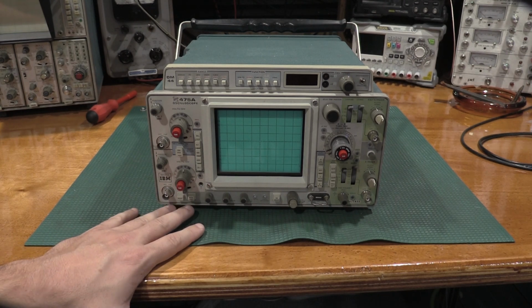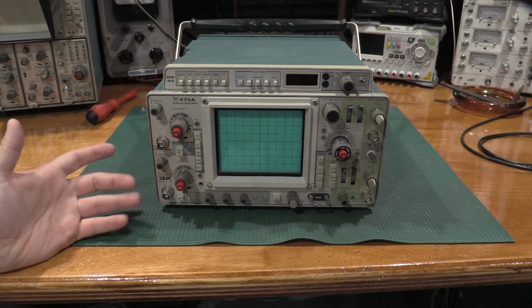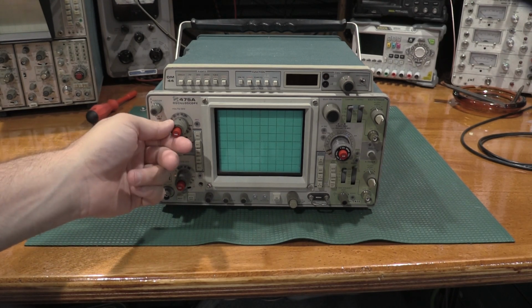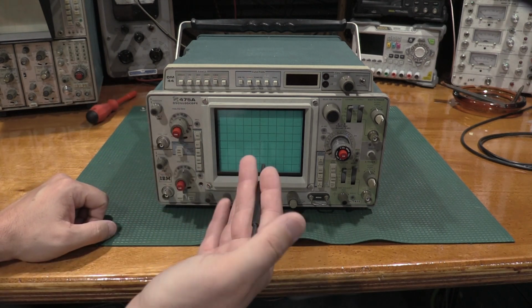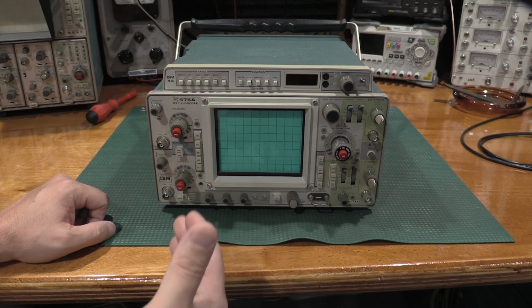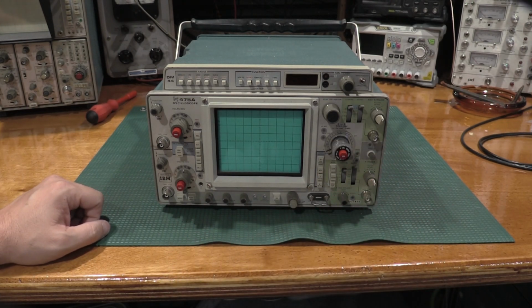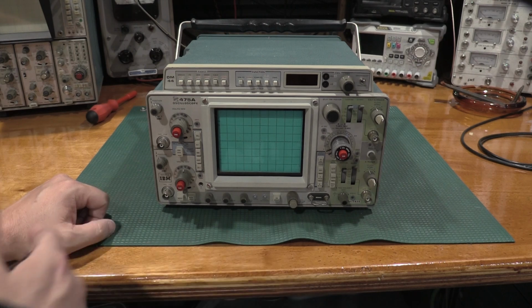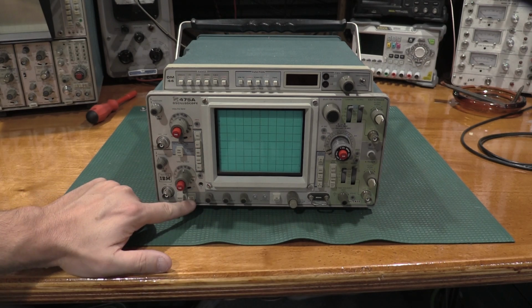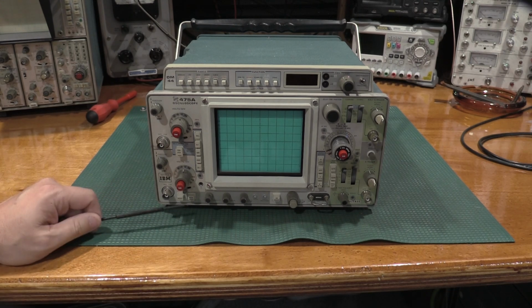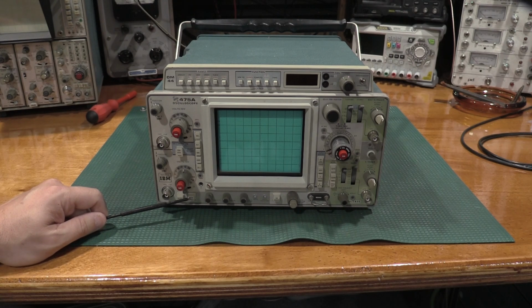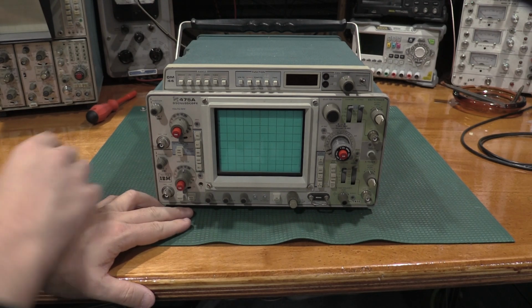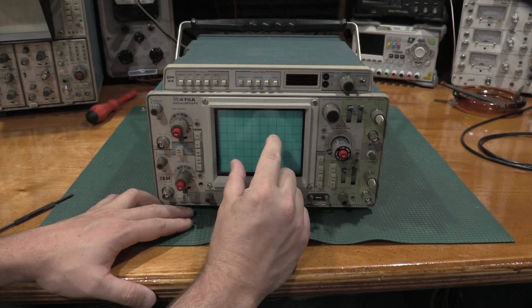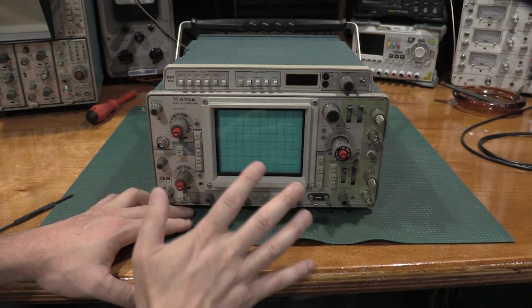So if you're running into unexplained noise that just doesn't seem to go away, that doesn't make sense for any of the other controls, like attenuator noise is pretty easy. That's in the vertical only, but not the horizontal. If you see horizontal noise and you're not adjusting the horizontal control, or you get horizontal noise with vertical control, hit this beam finder switch and clean this really, really well, because the CRT drive signals go through there. What this does is it compresses the screen, so it doesn't matter where the beam is positioned on the screen, you can find it.